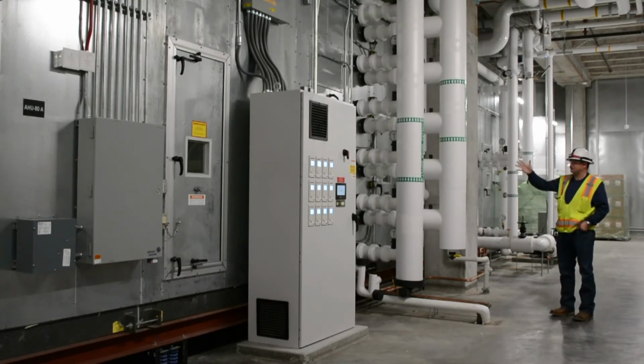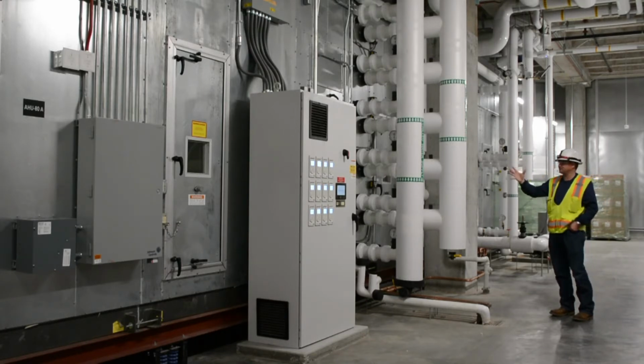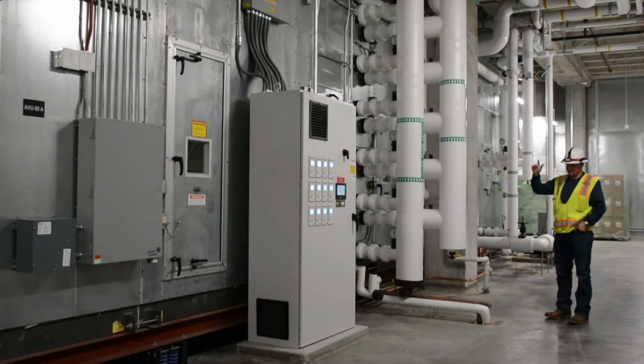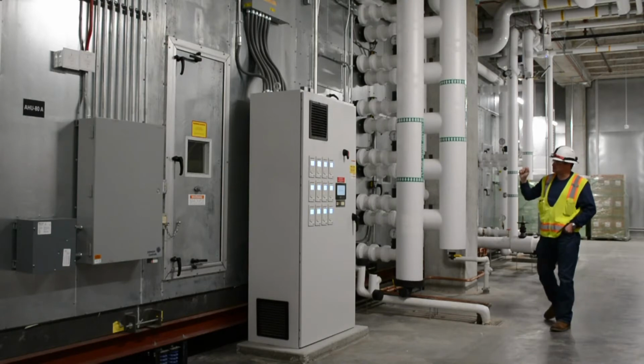Then the next item we have are the freeze stats for freeze protection of this chilled water coil. The chilled water coil also modulates to maintain discharge air set point in the summertime. If in the event that there's an issue with the preheat, that's where these freeze stats would trip to protect this coil from any breakage or freezing. The Metasys system will report an alarm if one of these has tripped. Due to the sheer size of the coil, we have multiple freeze stats in multiple locations that are all in a series configuration. Therefore, any one of them could be tripped, so you'll have to check all of them, not just one of them.